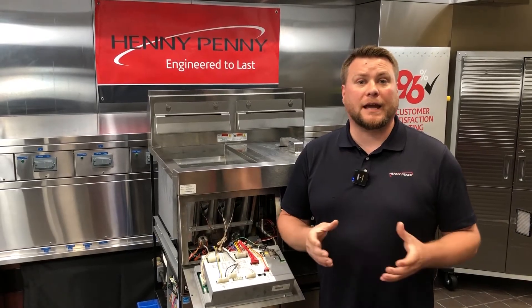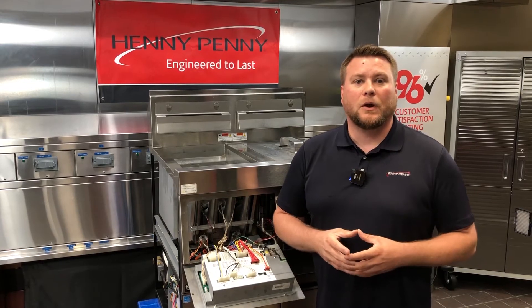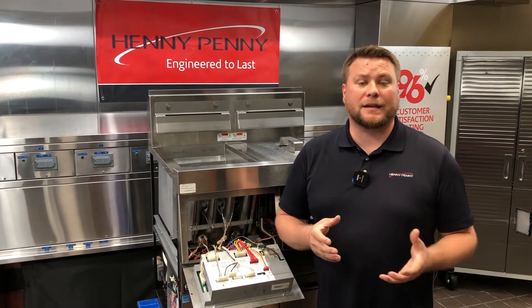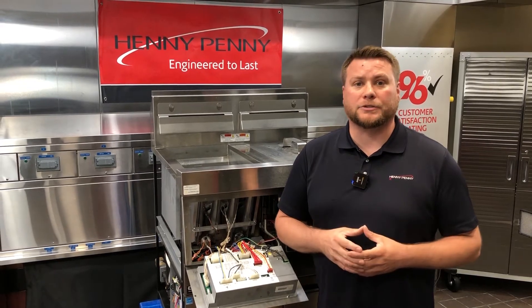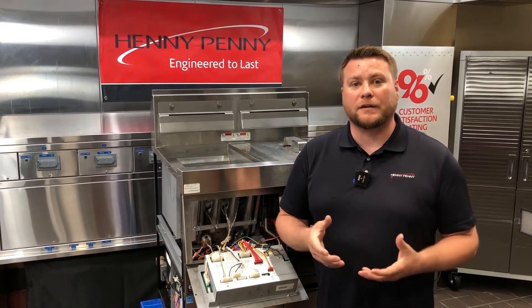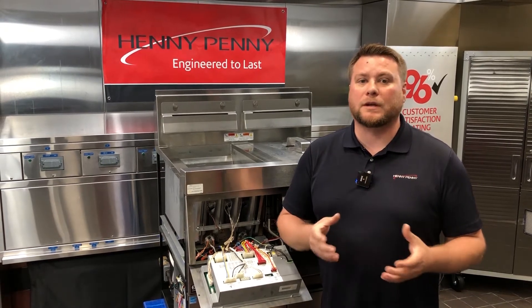In this video, I'm going to show you how to check the gas pressure on your LVG and your EVG fryers. I'm going to show you how to check both your static incoming supply pressure, as well as your dynamic pressure, which is going to be your outgoing manifold pressure, and how that reading is going to be much more important when it comes to troubleshooting.